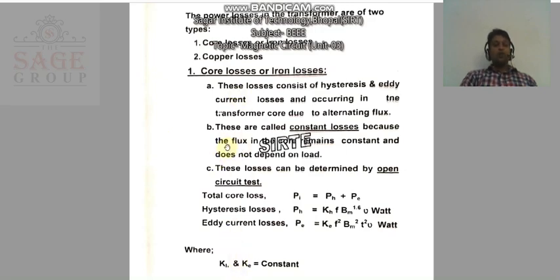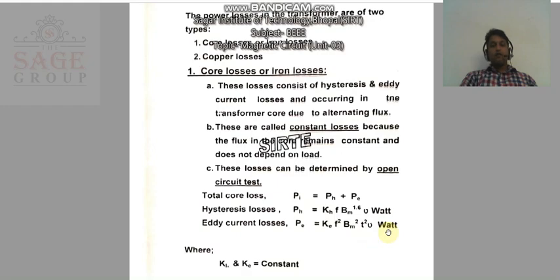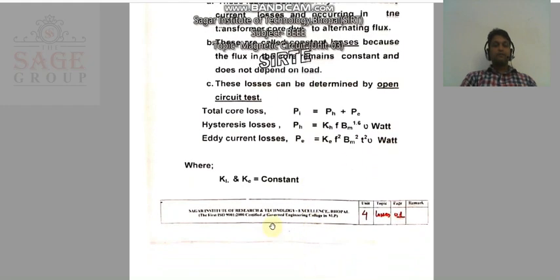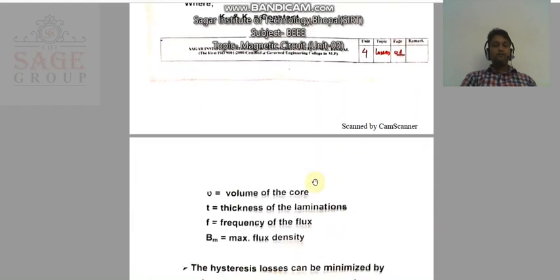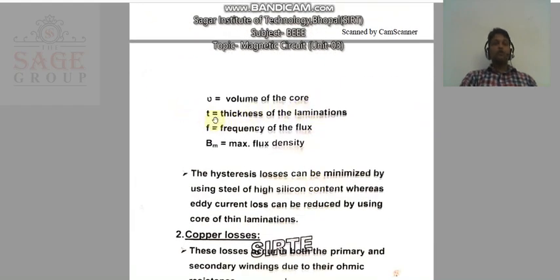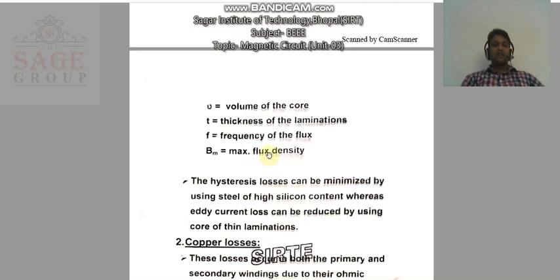The formula for eddy current loss, also denoted as PE, is: PE = KE × F² × BM² × T² × V. Where KE is a constant, V is the volume of the core, T is the thickness of the lamination, F is the frequency of the flux, and BM is the maximum flux density.